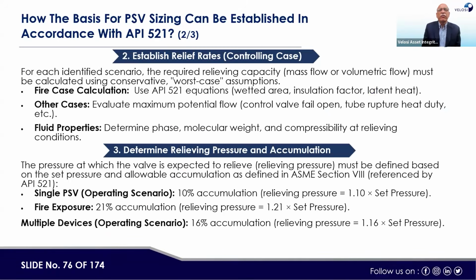Then, like we said, the fire case. For example, if there's a fire outside, which is a negative scenario, if fire comes, then things are out of control. Let's say thermal expansion: take a scenario of a system going from winter to summer. If there's a high temperature, like summer in the desert, it could be 50 or 70 degrees Celsius or even 80 on the metal temperature. If there is a liquid inside and no outlet open, the liquid may convert into vapor, and that vapor will overpressurize the system. If the system is overpressurized, a pressure vessel can burst. In that scenario, we need to provide a thermal expansion relief valve.